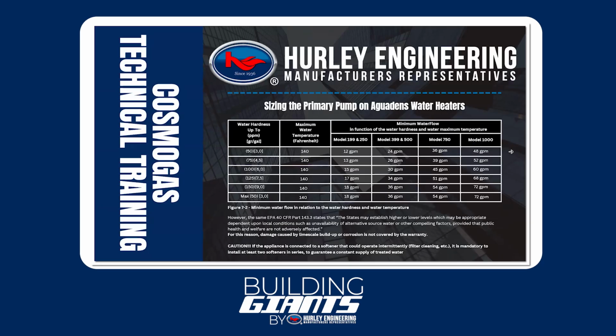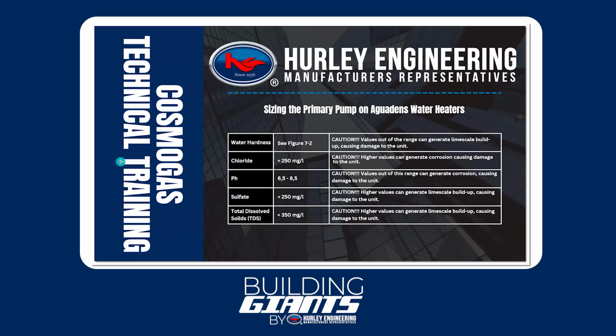Daryl, so if you run well water or something to that effect, because we have a lot of that here in Idaho, they'd have to have some kind of filtration ahead of that before it goes into the water heater itself. You can. So it just depends. You know, every well is a little different, and water hardness is definitely an issue. Total dissolved solids and grains per gallon. So softeners, just to remove that, but occasionally it's not just a hardness issue.